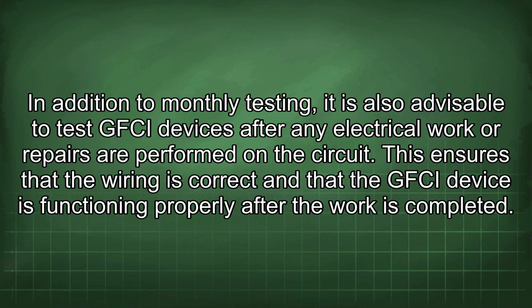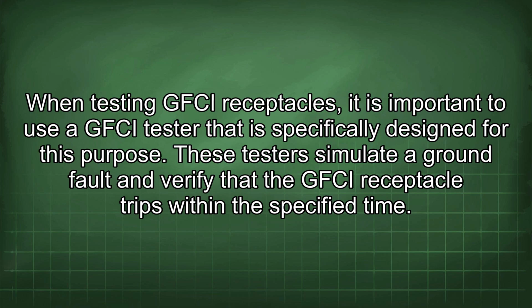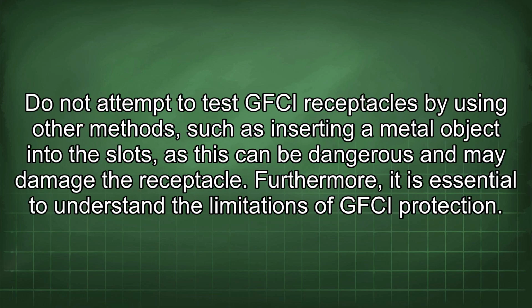In addition to monthly testing, it is also advisable to test GFCI devices after any electrical work or repairs are performed on the circuit. This ensures that the wiring is correct and that the GFCI device is functioning properly after the work is completed. When testing GFCI receptacles, it is important to use a GFCI tester that is specifically designed for this purpose. These testers simulate a ground fault and verify that the GFCI receptacle trips within the specified time. Do not attempt to test GFCI receptacles by using other methods, such as inserting a metal object into the slots, as this can be dangerous and may damage the receptacle.